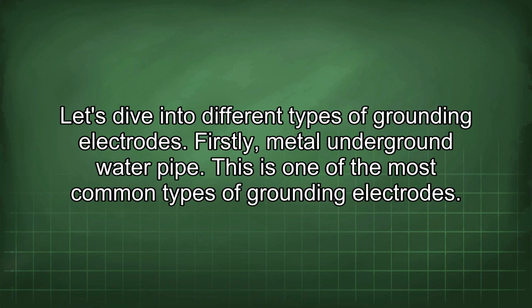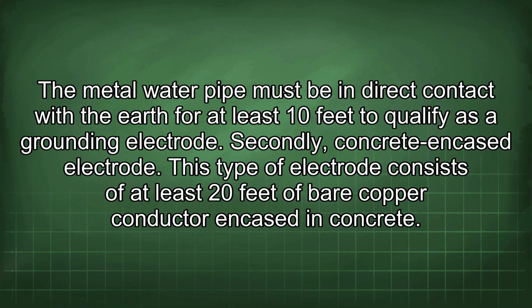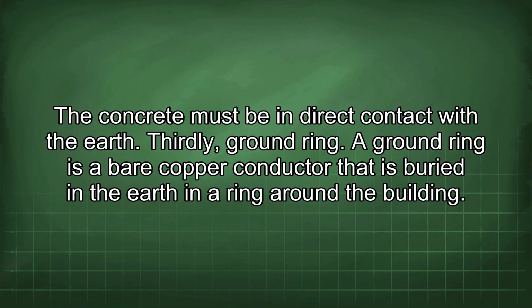Firstly, metal underground water pipe. This is one of the most common types of grounding electrodes. The metal water pipe must be in direct contact with the earth for at least 10 feet to qualify as a grounding electrode. Secondly, concrete encased electrode. This type of electrode consists of at least 20 feet of bare copper conductor encased in concrete. The concrete must be in direct contact with the earth.